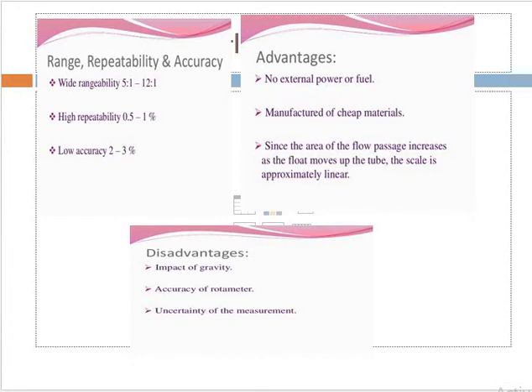The range of repeatability and accuracy and the advantages: there is no need for external power — no direct current or AC current is required. It can be manufactured with cheap materials such as brass, steel, plastic, or aluminum. The annular area increases as the float moves up due to upthrust, and the scale is approximately linear. It has a wide rangeability of 5:1 to 12:1.